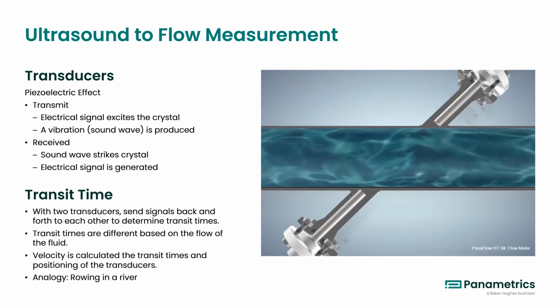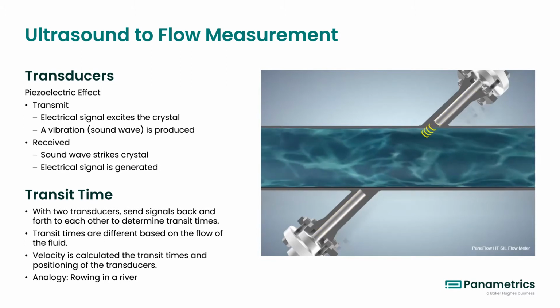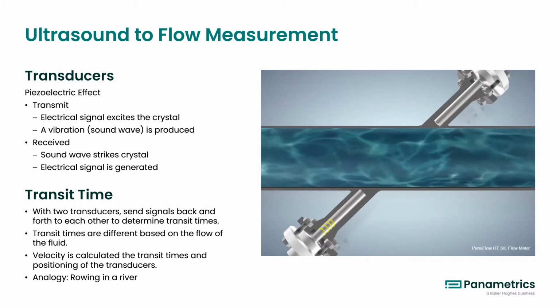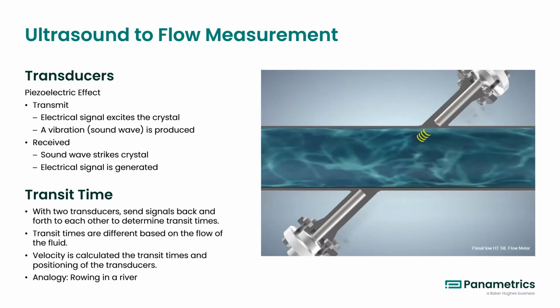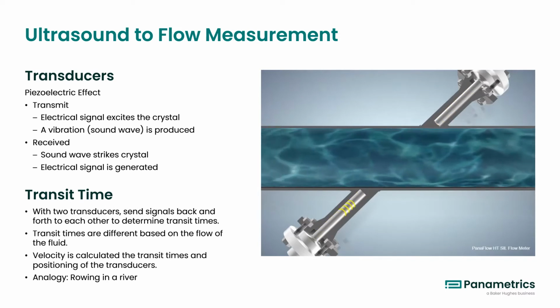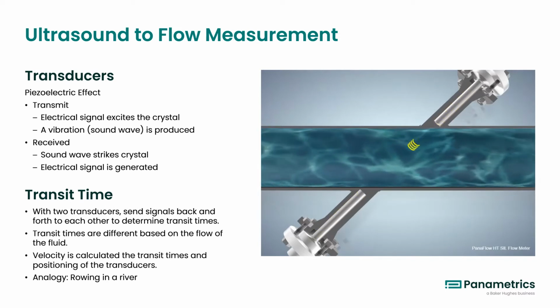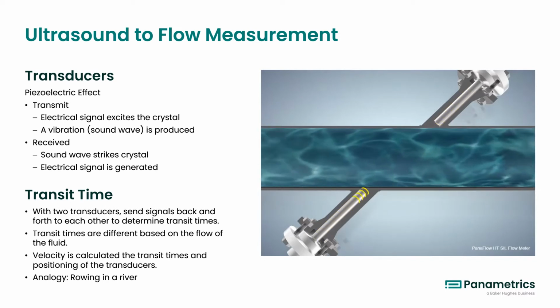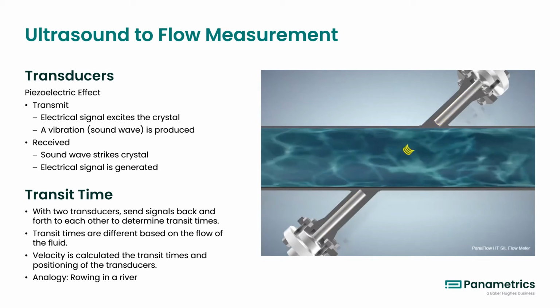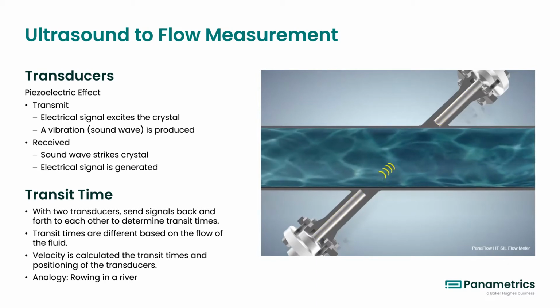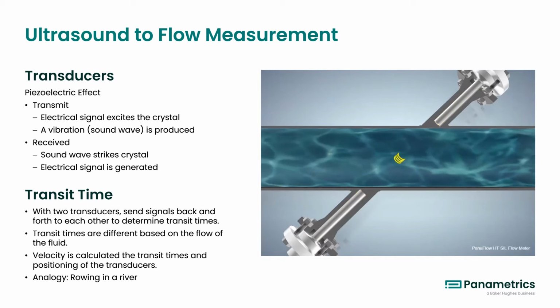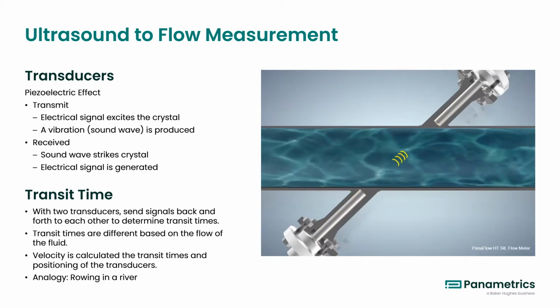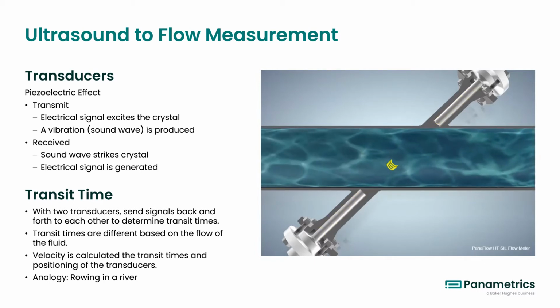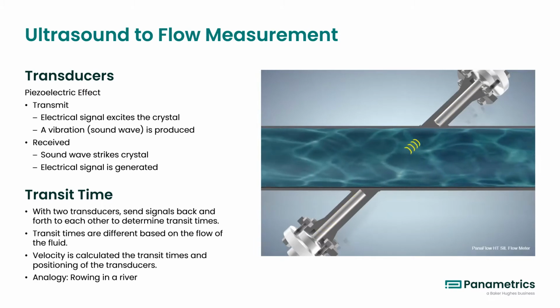However, when there is flow in the pipe, the signal from the downstream transducer will slow down as it goes against the process fluid to the upstream transducer. The opposite occurs as the signal from the upstream transducer will speed up going through the process fluid to the downstream transducer. This time difference is proportional to velocity. By knowing the pipe dimensions, a volumetric flow measurement is determined, and mass flow measurement is determined when the density of the fluid is known.